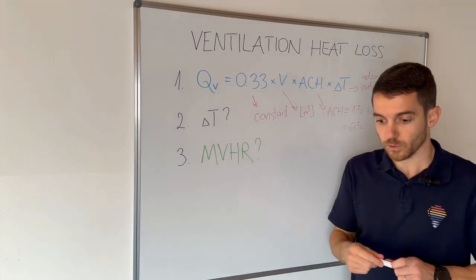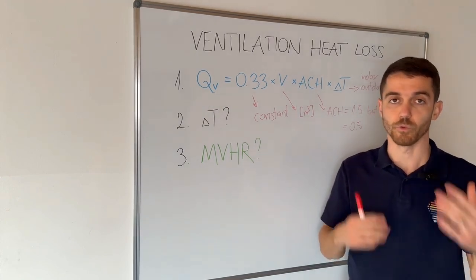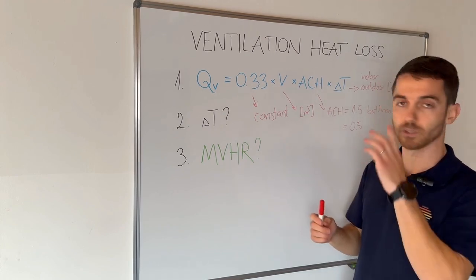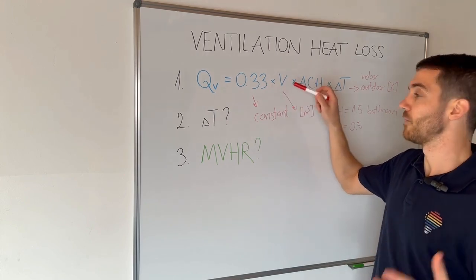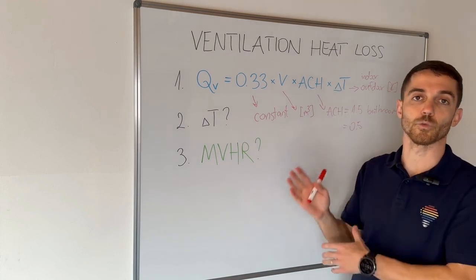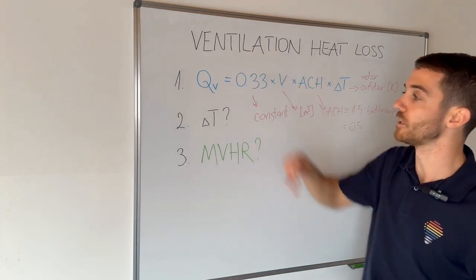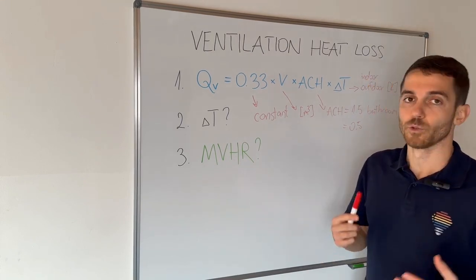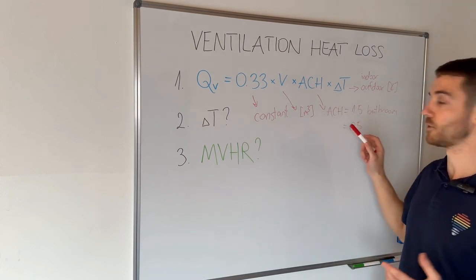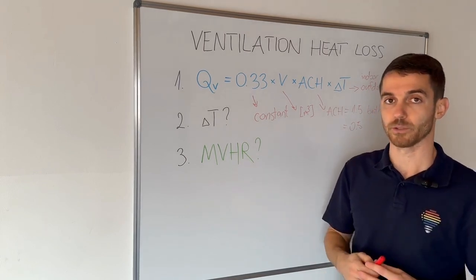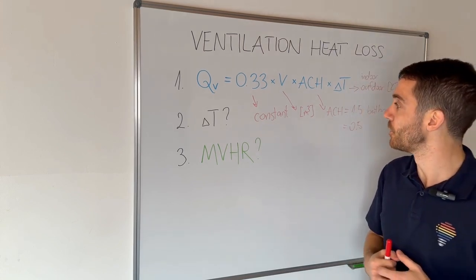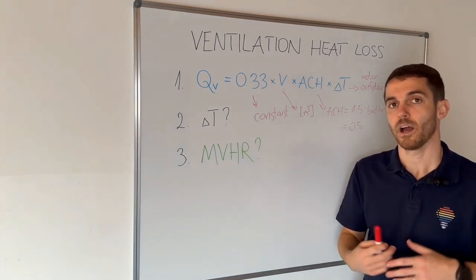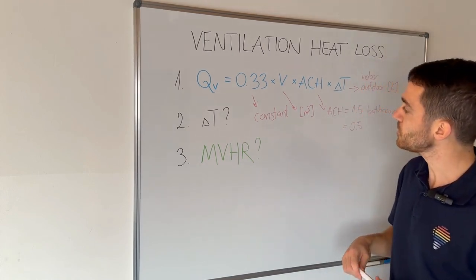The first important thing to understand is that when we are dealing with calculations and formulas, we are usually talking about static conditions. For example, in Croatia, the design outdoor temperature is minus 10 degrees. But when outdoor is minus 10, I assume no one will have 1.5 air changes per hour in the bathroom or 0.5 in another room. In my opinion, I think we are overestimating ventilation heat loss.